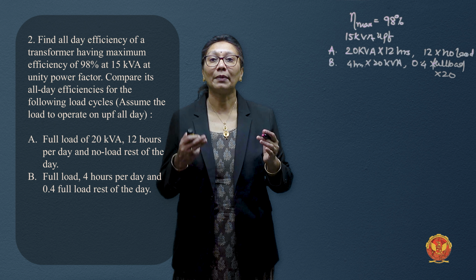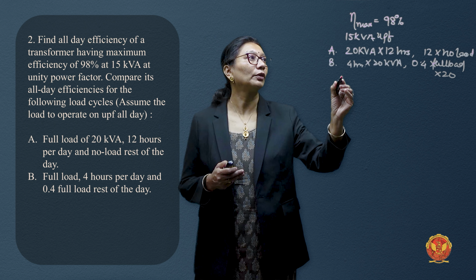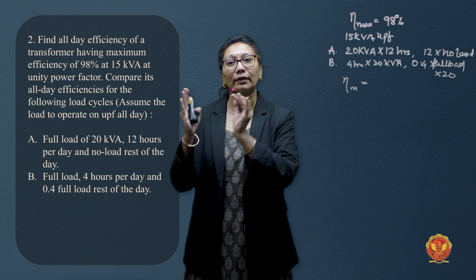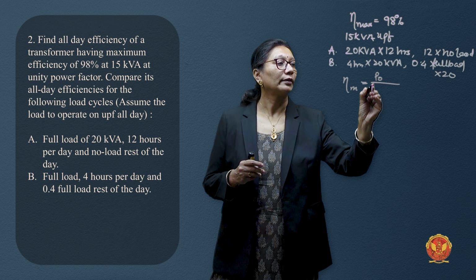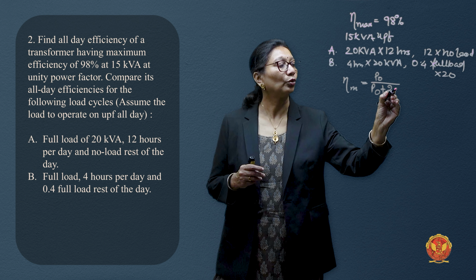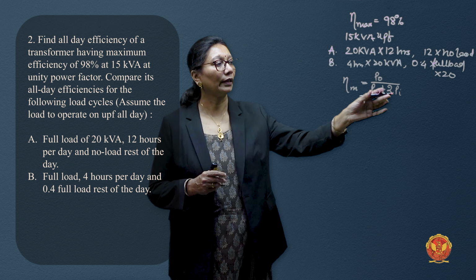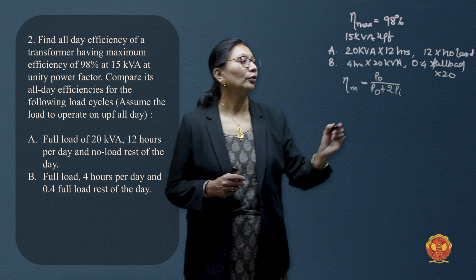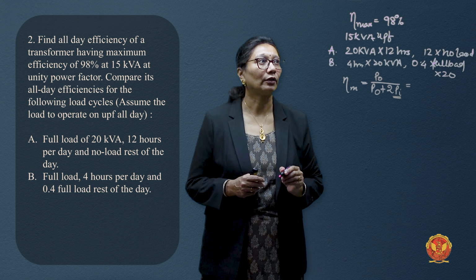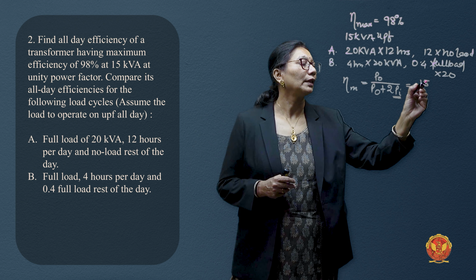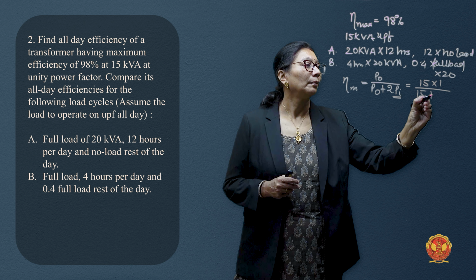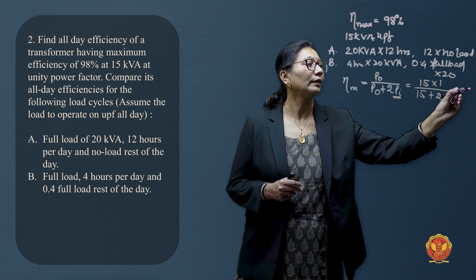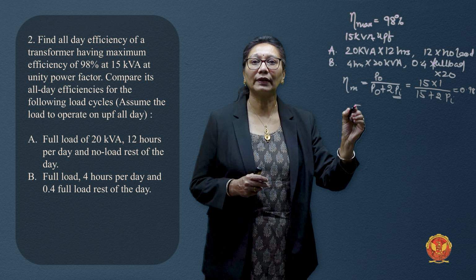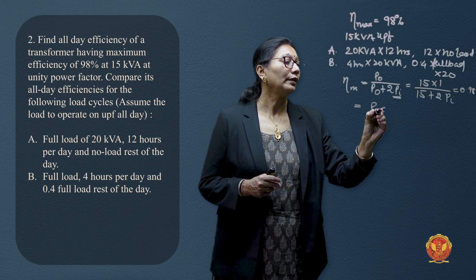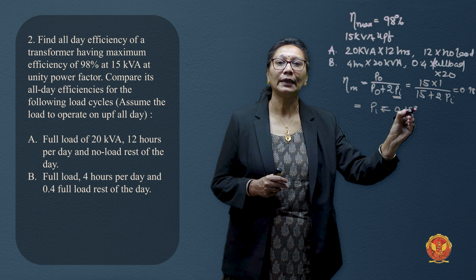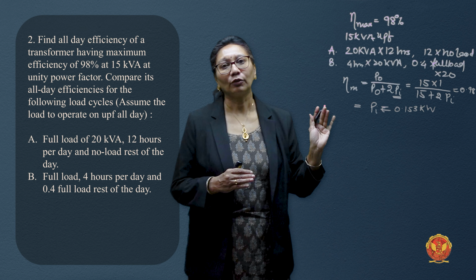Since maximum efficiency is given, when does maximum efficiency occur? It occurs when iron losses are equal to copper losses. Expression-wise, P output plus 2P iron losses gives the input power, where P output is the output power. From here you can calculate the value of iron losses. We are given output as 15 kVA at unity power factor. So 15 divided by (15 plus 2Pi) is 0.98. This gives Pi equal to 0.153 kilowatt.